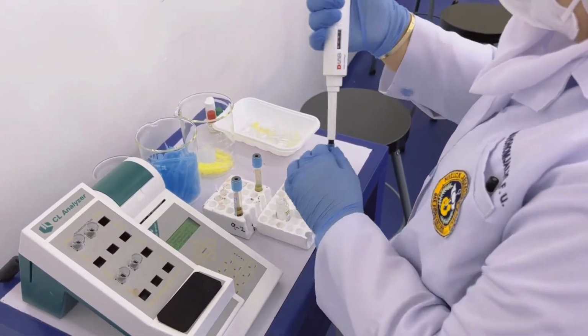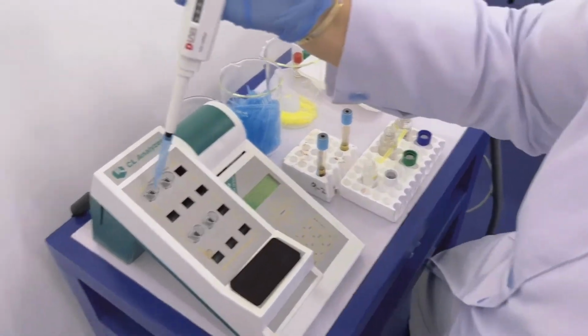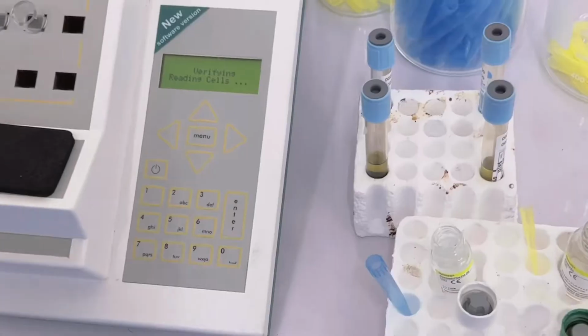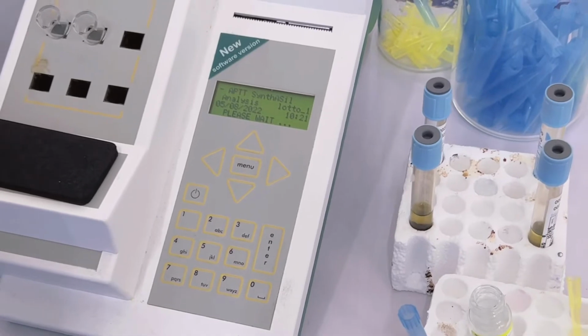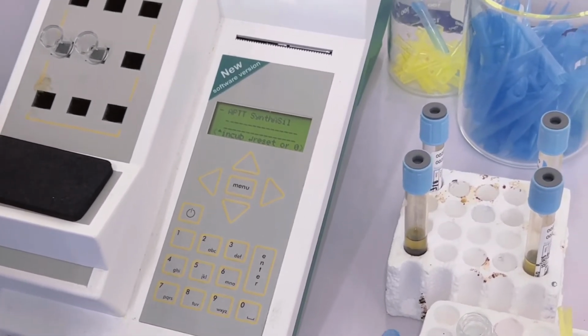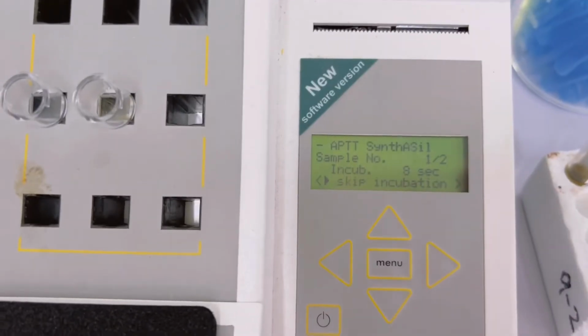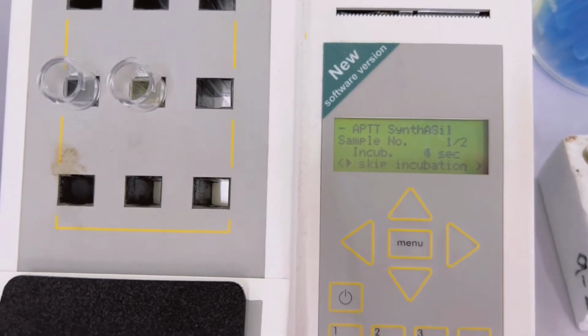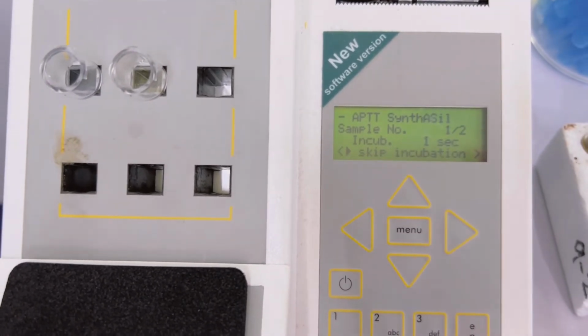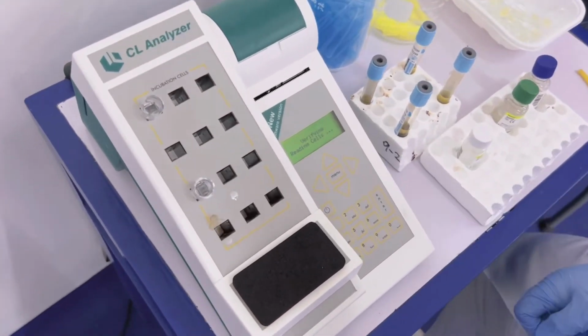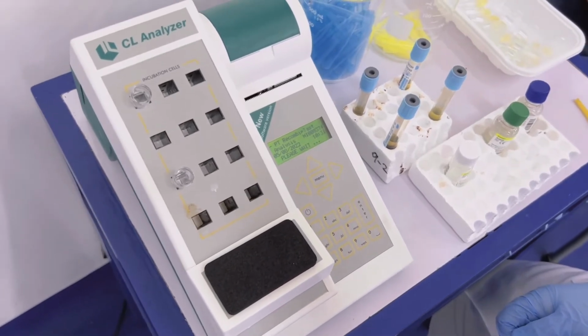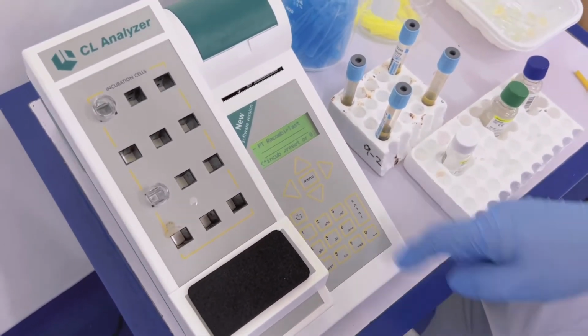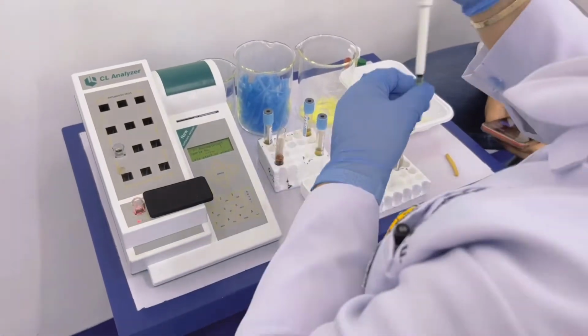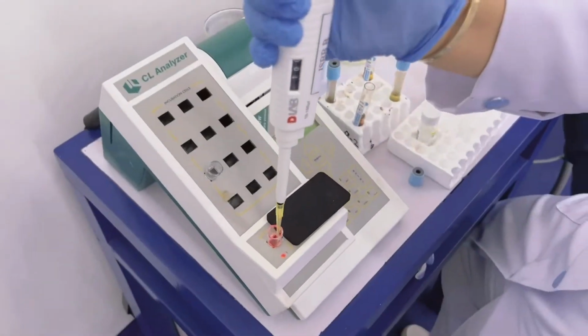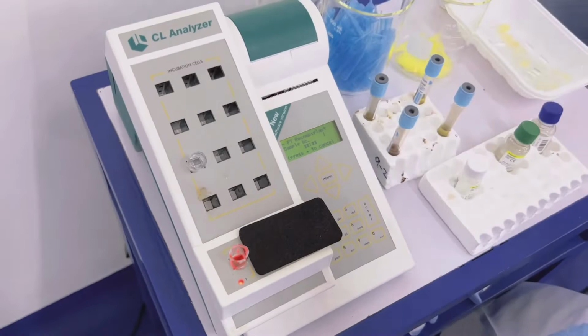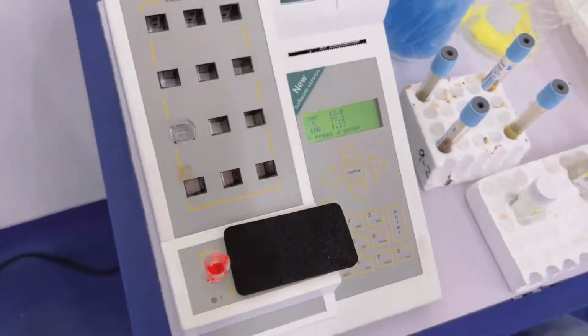Prothrombin time using CL analyzer. First step is to add 200 microliters of the reagent into the cuvette. Next is to incubate the reagent in the machine. After incubation, you can now do the testing. Put the cuvette into the reading cell chamber and add the plasma. After adding the plasma, the machine will run the test and the result will be flashed on the screen. Always remember to dispose of the cuvette.